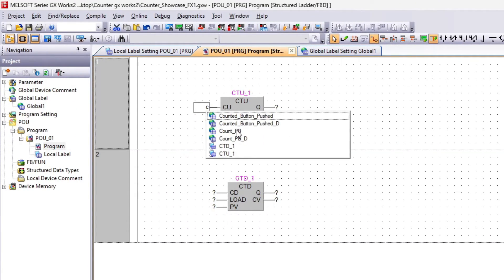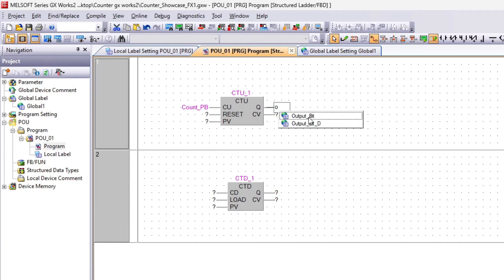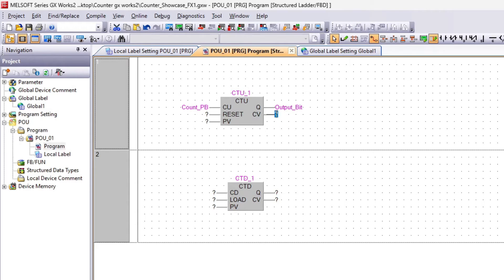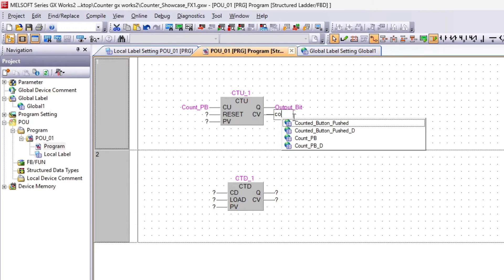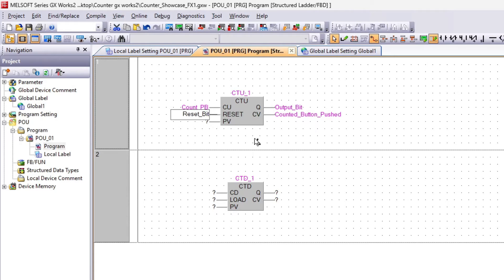The CU stands for CountUp and is the input trigger that will make the block count up. Q is the output bit that will go high once the preset value is reached. CV is the output that will count how many times the CU has been triggered. The reset input will reset the counter value, and PV is the preset value.